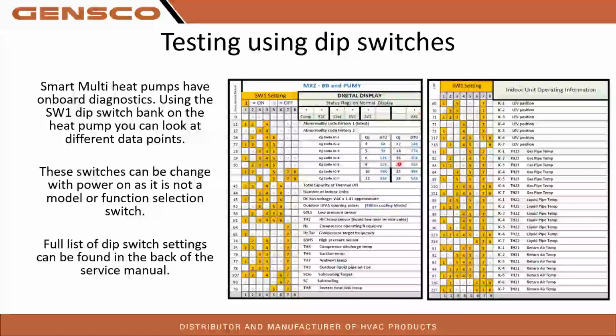If I flip it on and I only see 0 or 1 or 2 or something like that, then I know I'm having communication problems with my indoor equipment. So start doing some diagnosing on that, checking for crosswire. Did they swap S2, S3? Do they have the Mnet hooked up? Did they run the wrong wire? Is everything powered? Going through testing and all that kind of stuff. Like I said, there's a lot of.